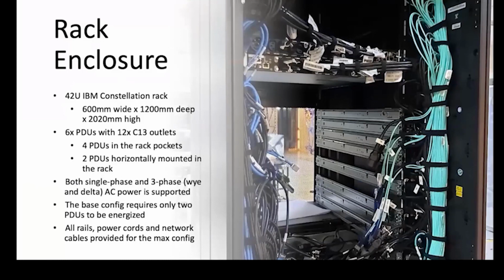Every component is plugged into 2 PDUs for redundancy because all the switches and servers in Spectrum Fusion HCI come with 2 power supplies, and each of those power supplies is connected to a different power distribution unit, again, for redundancy and to remove as many single points of failure as possible. There are different options for powering the rack. Both single-phase and 3-phase power is supported, AC power, and the 3-phase power can be either the Y or Delta type, depending on what geography the rack will be installed.